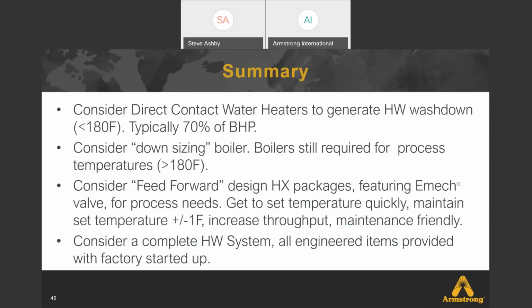So we would suggest that you first address steam boilers, if in fact that's what's being used for generating your washdown water, and consider direct contact heating for this application and shed that load from existing steam boilers. This would allow you to consider then downsizing the boiler. We're never suggesting getting rid of boilers altogether, because there are applications in the plant that require temperatures greater than what direct contact can offer. So there's always going to be a need for steam.